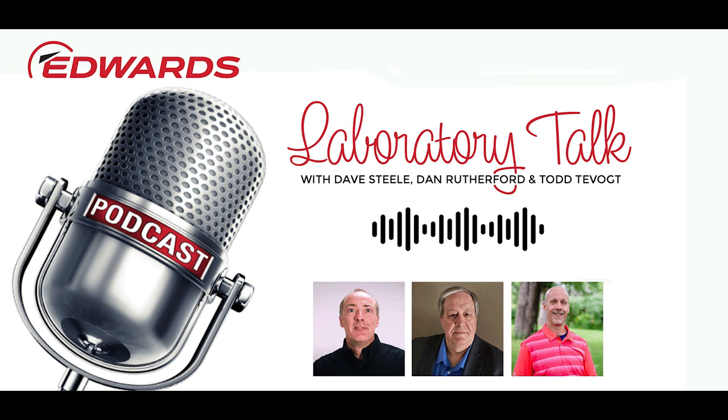This enables the gauge to give usable indication all the way to atmospheric pressure and improved accuracy in its normal ranges. Because I think before we didn't give an accuracy specification on the Pirani gauges above, you have to correct me if I get this wrong, 100 millibar. So above 100 millibar, they were kind of indication only. That's down to the technology inside a Pirani gauge. You have to use different measurement techniques at higher pressures. Exactly. This is always an interesting point. You're exactly right, Dave.